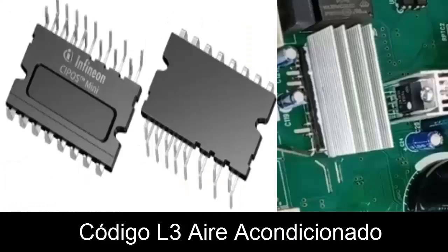7. Ensure that the IPM output pins have continuity with the connector where the external unit's fan connects.